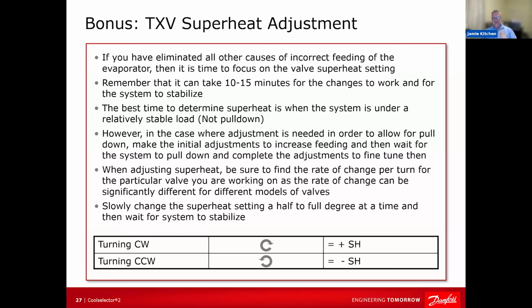Now, it's also important not to be in too much of a hurry. So you are commissioning a system, you're starting it up, you're firing up the system. A lot of times there's going to be no product inside of this if it's a brand new build. And so what you're doing is slowly pulling it down. You don't want to pull down too quick because you don't want to mess up the concrete and everything, but you're slowly pulling it down. So what you're going to see is your superheat's going to go way up and then it's going to come down. Because remember, the mass of air that's inside that cooler is a fraction of the mass of the rest of the cooler itself and the floor and whatnot.